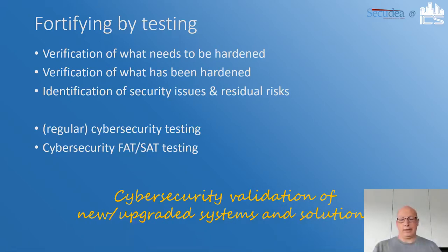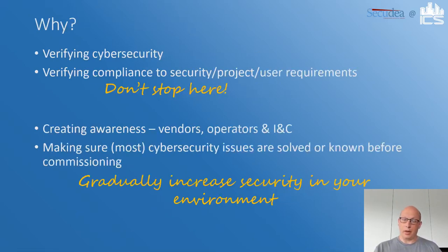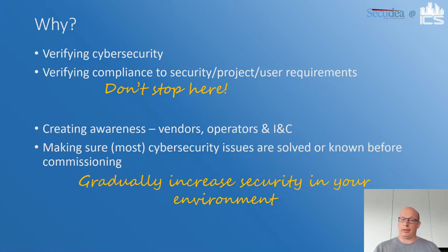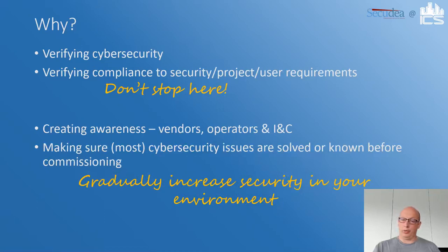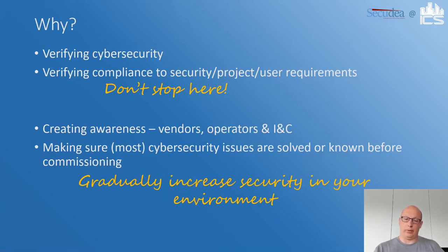Cyber security FAT testing is the cyber security validation of new or upgraded systems and solutions. Why do cyber security testing in ICS environments? First, verifying cyber security. Second, verifying compliance to cyber security or project requirements — but you should not stop there. By doing testing you also create awareness with vendors, operators, and ICS people, ensuring most cyber security issues are known and are candidates to be solved before commissioning. Cyber security testing together with hardening and FAT/SAT testing will gradually increase your security.